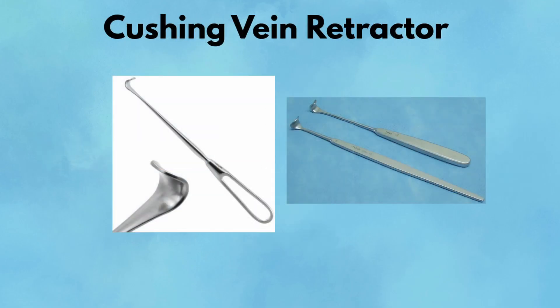Cushing Vein Retractor. The Cushing Vein Retractor is a small, angled, handheld retractor designed to gently lift veins and soft tissue aside. Its low profile and subtle curve allow for precise exposure in areas like the neck, axilla, or groin, where vital vascular structures lie just beneath the surface. In carotid endarterectomy, for example, this retractor exposes the artery without compressing adjacent veins. The slim handle and minimal bulk allow assistants to hold it comfortably without obstructing the view. The retractor's design follows the natural contours of vascular anatomy, minimizing risk.